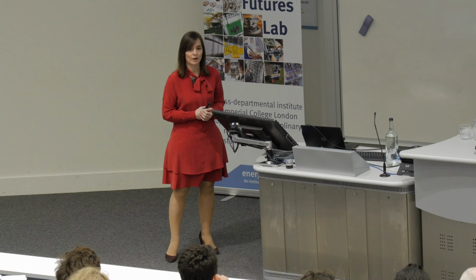One of the challenges I mentioned before was about bidirectional flows. How do you keep your protections working when you have less short-circuit strength, and when your flows and the properties of the grid change continuously? You would need to remotely and automatically upgrade the protection settings. That seems easy, but it's actually a very difficult task if you don't take this step through the digital substation and the complete new software platform around it.